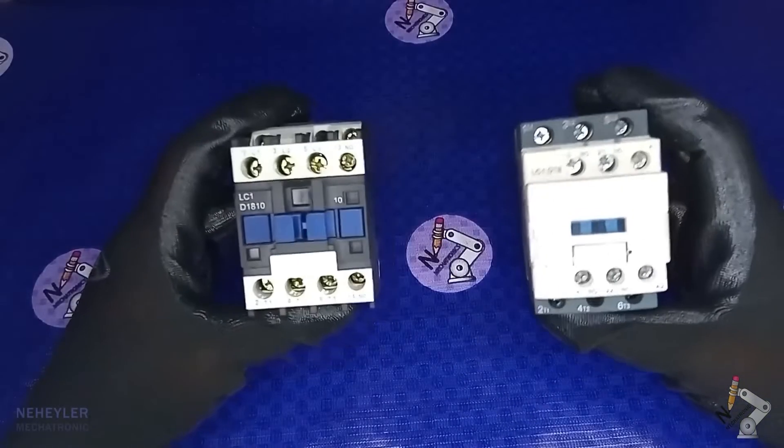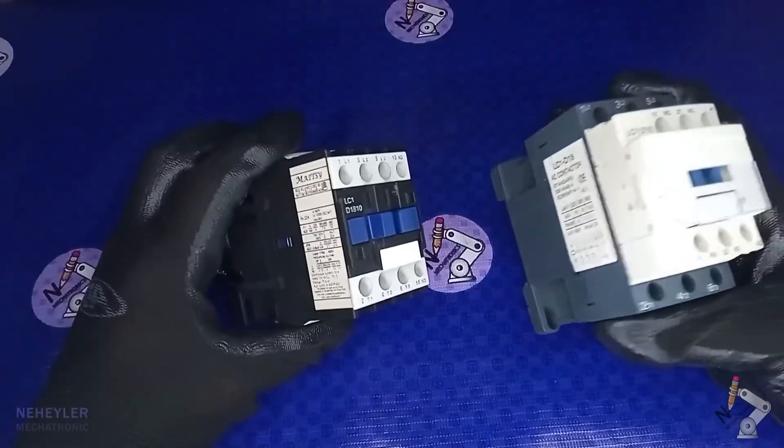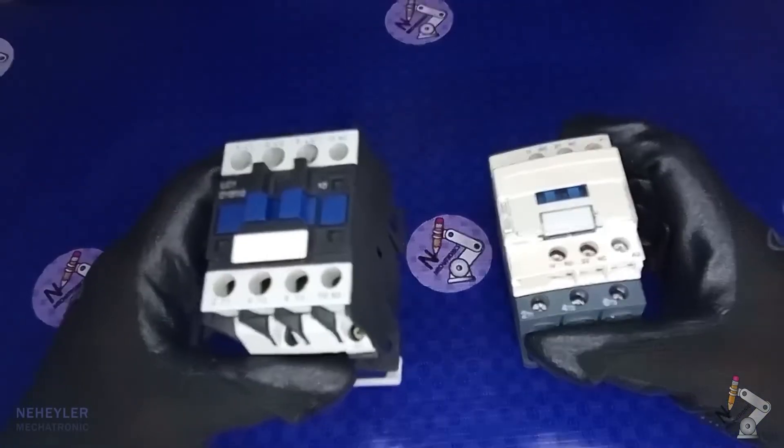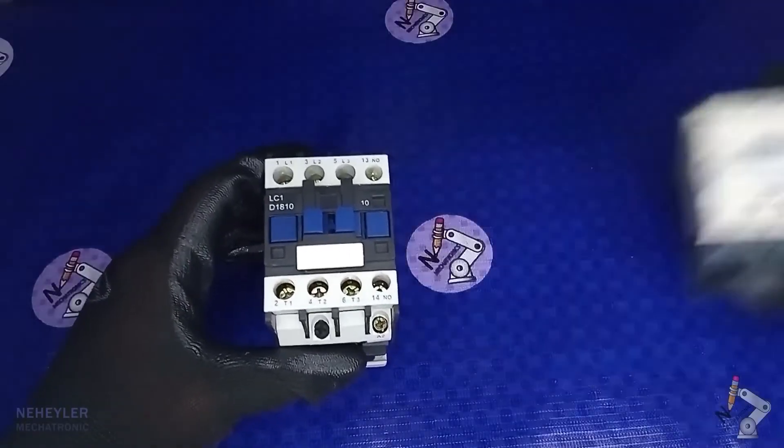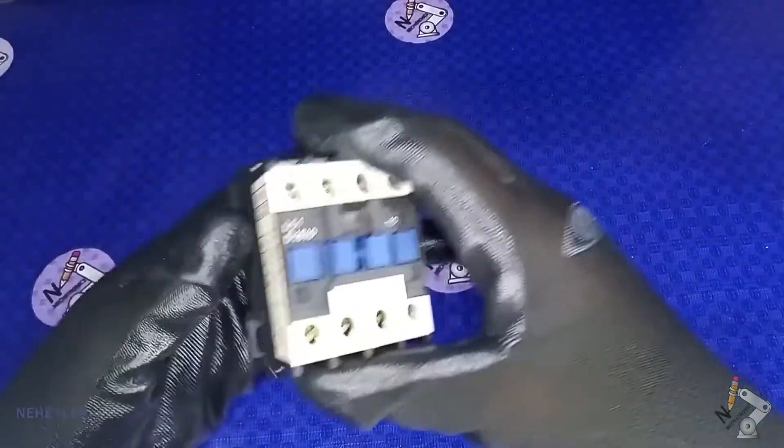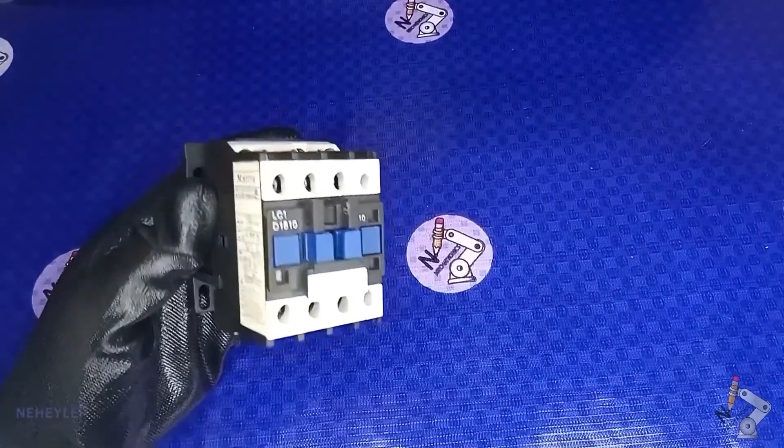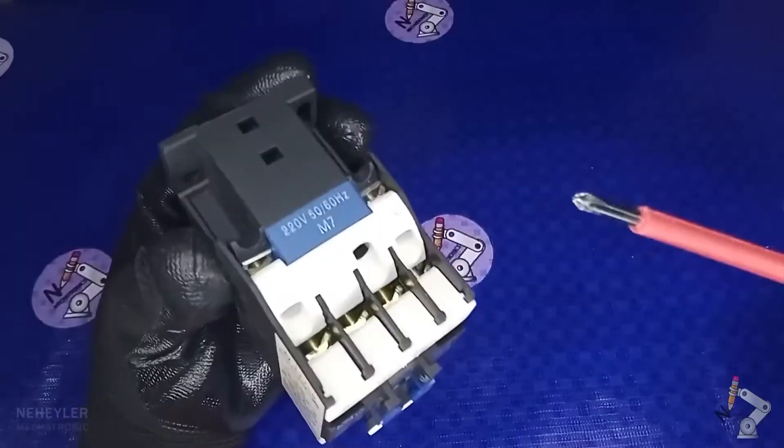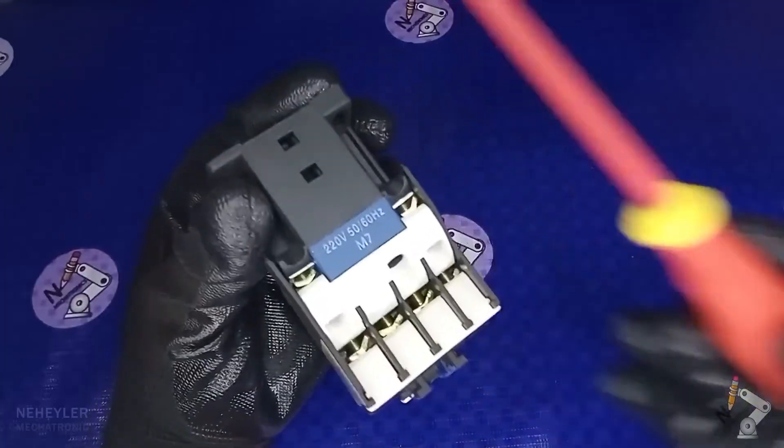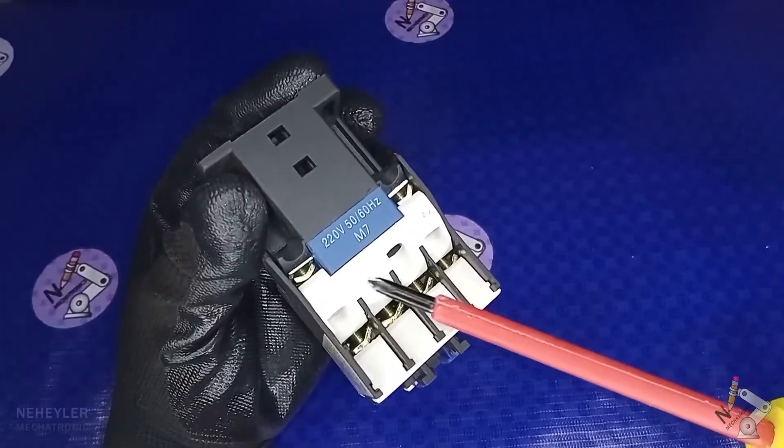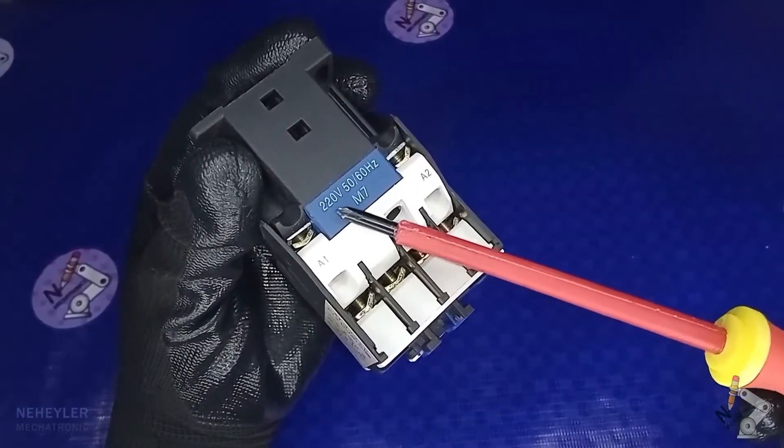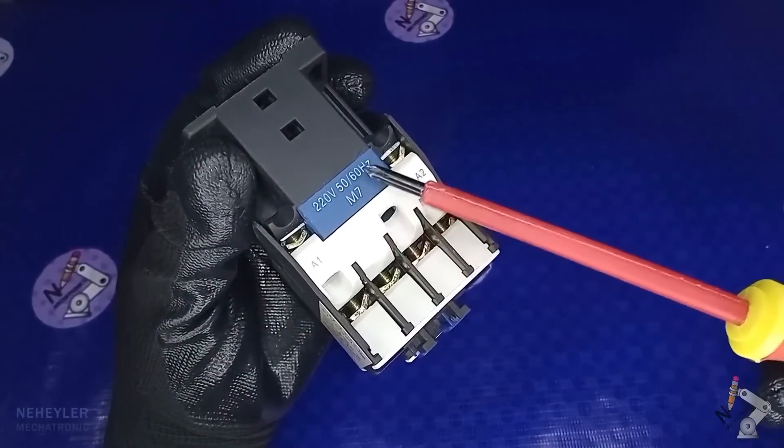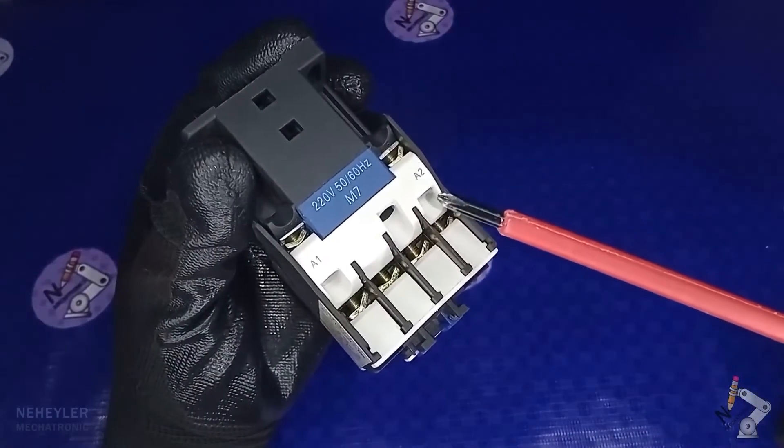Here I have two electromechanical contactors of different models and brands. Let's briefly look at the external parts of this contactor, since the other one is also similar. This device is made up of three fundamental parts and they are the coil, which is basically an electromagnet, whose connecting terminals are at the top. Here it indicates that the coil must be powered with 220 volts at 50 or 60 hertz.